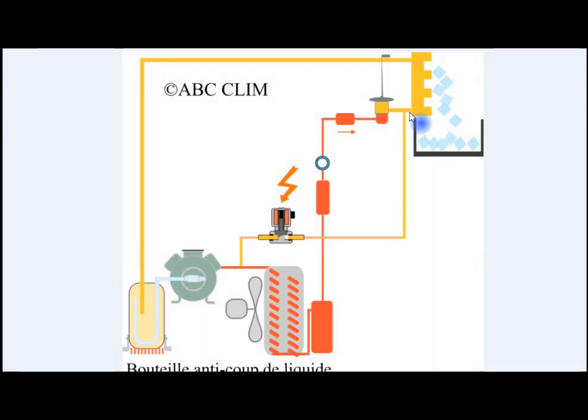Since the evaporator turns into a condenser, the liquid will return to the compressor. But to avoid damaging the compressor, we have an anti-slug liquid device which is equipped with a resistance to evaporate the liquid to protect the compressor. This is a simple function. We will see something more complicated now.